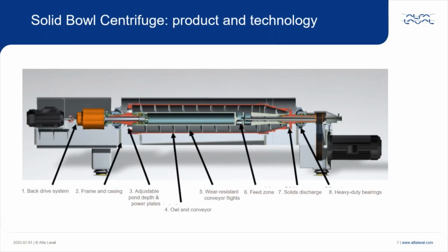You can see the solid bowl, made out of stainless steel or duplex steel at the center in red periphery. It's a bowl shell made out of solid stainless steel, and the shell thickness is something like 13 to 15 millimeters. So it's very strong, and it is centrifugally casted. It is cylindrical in shape, with a conical shape towards one end, the right side, as you can see in this picture.